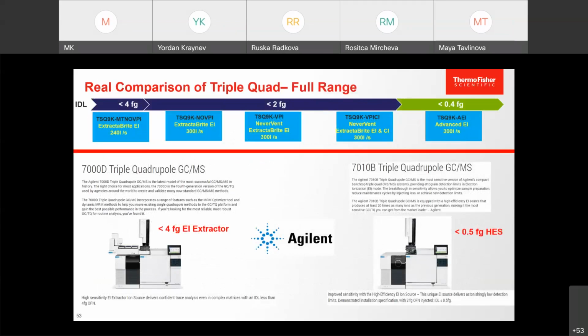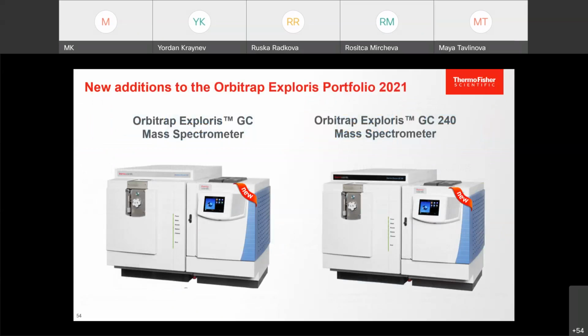Now we are looking at a triple quadrupole competitive comparison with Agilent. You can see our medium turbo pump is 4 femtograms, a 7000 series triple quadrupole GC-MS, and then the rest of our quadrupoles with a 300 liter pump is half of that. That means not 4 femtograms but 2 femtograms. And if we compare their HES, high efficiency source, the maximum is 0.5 femtograms. Our system is 0.4 femtograms. That means 20% better.